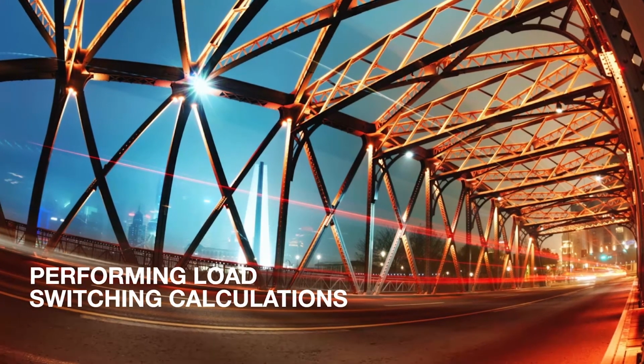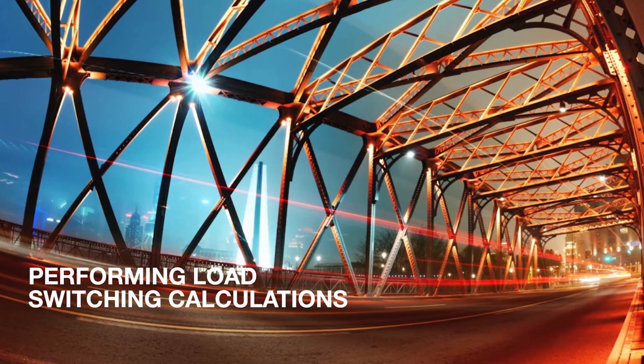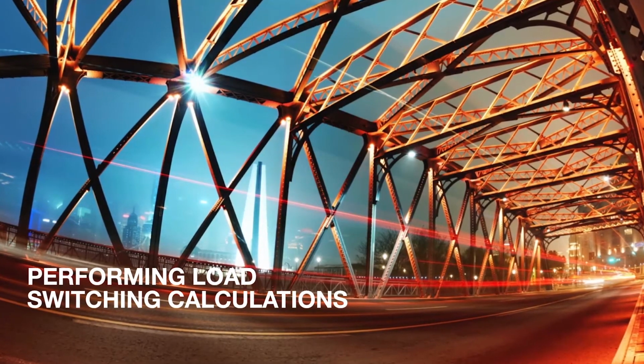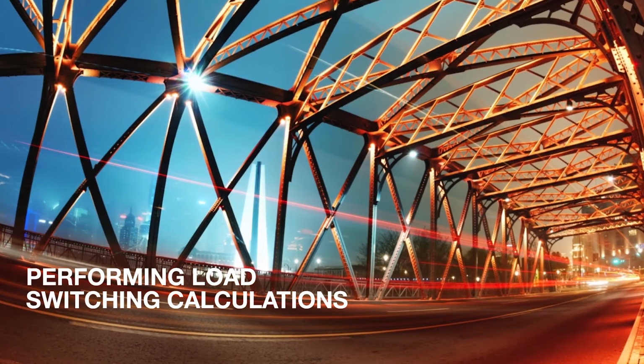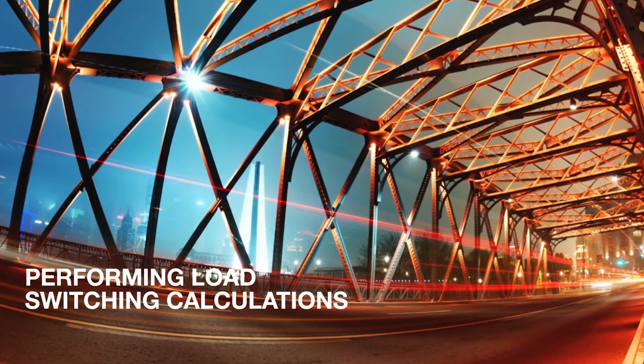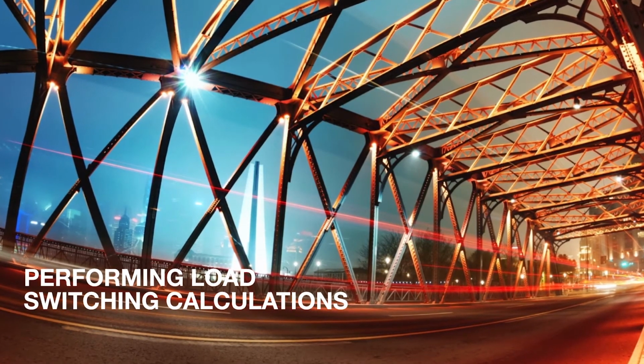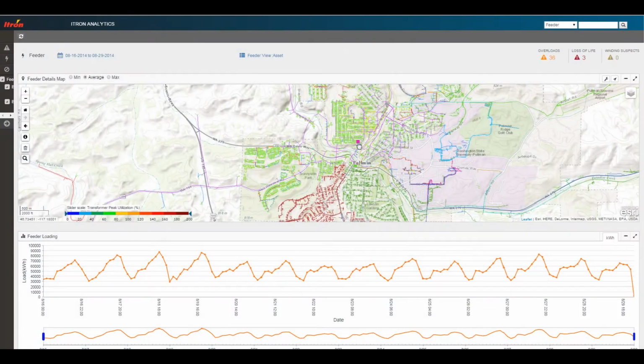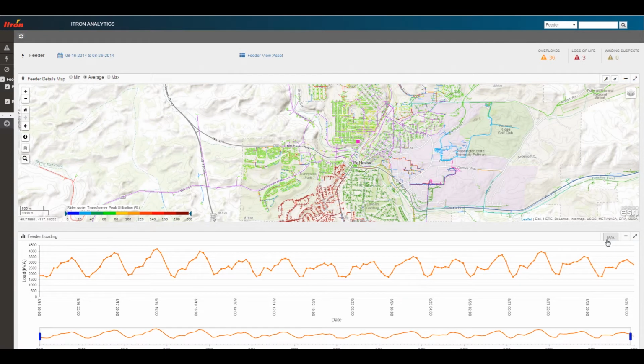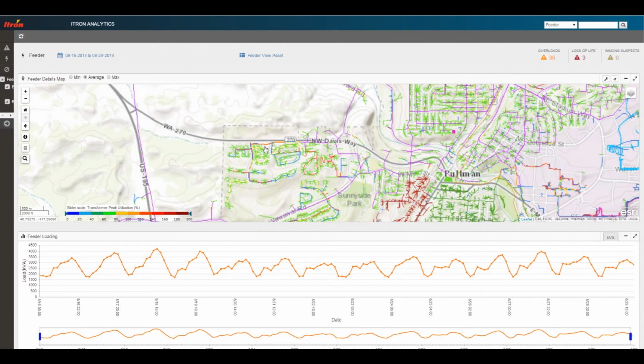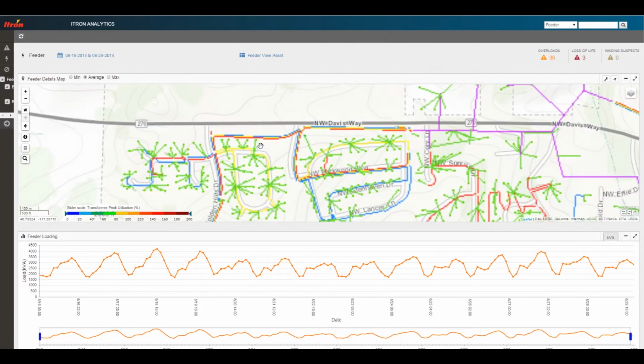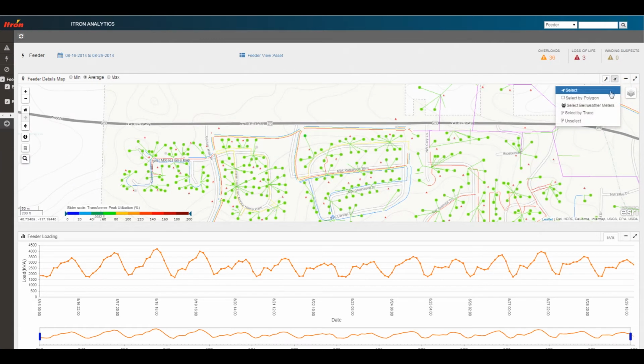In this scenario, an operator or engineer needs to calculate the load they can shift from an overloaded circuit to an adjacent one. This example demonstrates how the application combines AMI data with GIS circuit models to accomplish the task. The operator selects the overloaded circuit and chooses the date range when overload occurred. Hourly load profile data is displayed for the selected day. The operator or engineer can choose between kilowatt-hour usage and kVA demand displays.